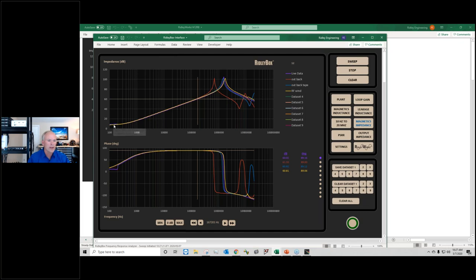But we can see the sweep right at the beginning here because it's different. When you're shorting the secondary, there's a little bit higher resistance at low frequencies. Sounds kind of funny, you short a turn and the resistance goes up. That's what happens in a transformer. It's kind of weird. Now we see our impedance stays low because we're dealing with leakage inductance instead of magnetizing inductance. And then it starts to rise right here.